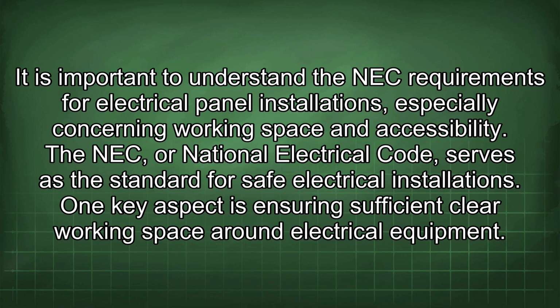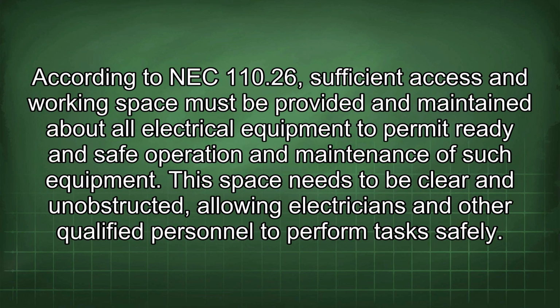The NEC, or National Electrical Code, serves as the standard for safe electrical installations. One key aspect is ensuring sufficient clear working space around electrical equipment. According to NEC 110.26, sufficient access and working space must be provided and maintained about all electrical equipment to permit ready and safe operation and maintenance of such equipment. This space needs to be clear and unobstructed, allowing electricians and other qualified personnel to perform tasks safely.